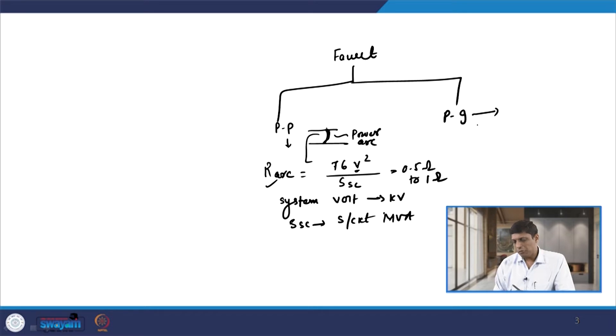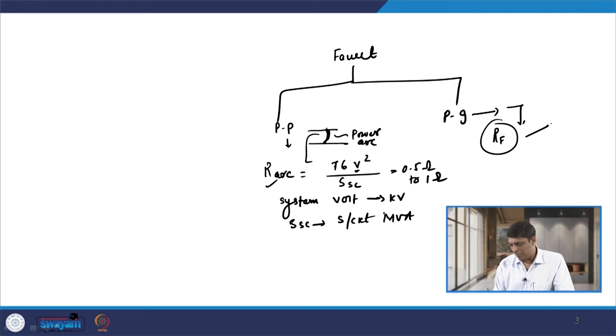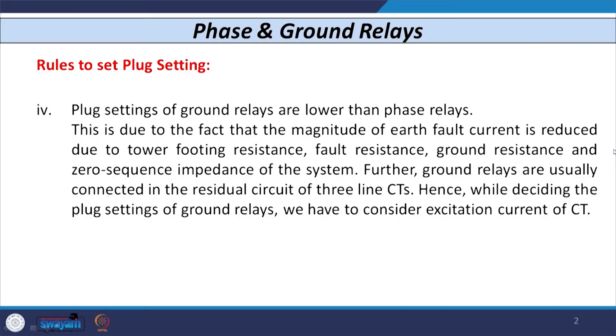But when you have a phase-to-ground fault, the involvement includes the fault resistance RF, which contains the tower resistance. The tower resistance usually varies from 5 ohm to 50 ohm. If we consider further the other resistance involved, it also contains the zero-sequence impedance of the system if the fault is asymmetrical in nature. That is why the magnitude of earth fault current is always lower than the magnitude of fault current in a phase-to-phase fault.